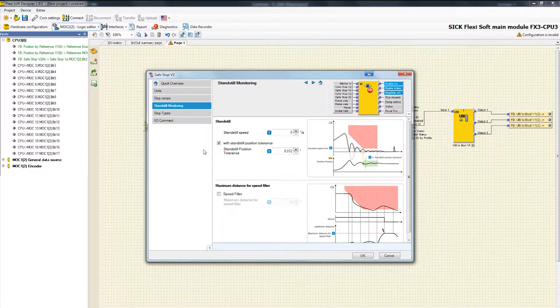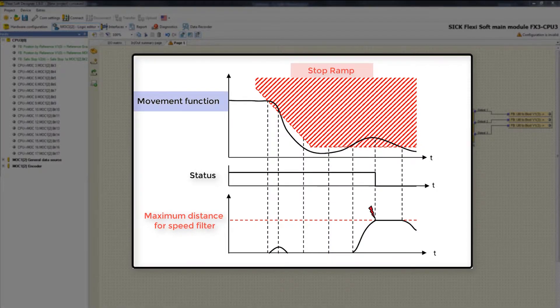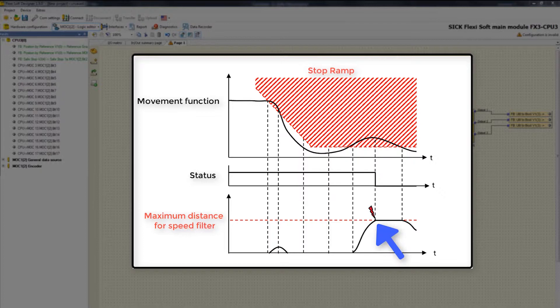The optional setting Maximum Distance for Speed Filter defines the distance the drive is allowed to move despite exceeding the maximum permitted speed. In the graphic, there is a defined maximum for the speed filter. At a point where the drive is moving at a forbidden speed, we calculate the additional position movement the drive makes in the forbidden area. If it didn't exceed the maximum distance, there is no reason for shutting down the torque. However, if the maximum distance is exceeded, the drive has moved too far while driving at a forbidden speed, so the torque is cut off and the output Status goes low because an error was detected.